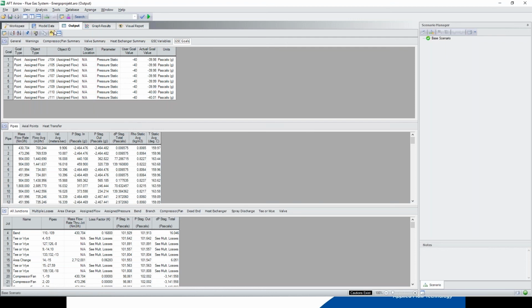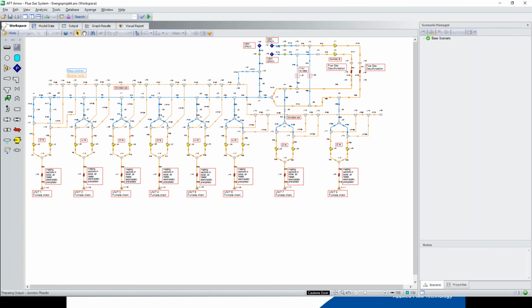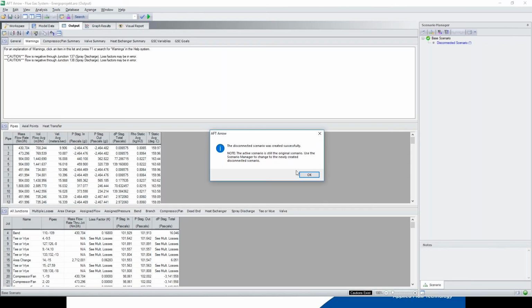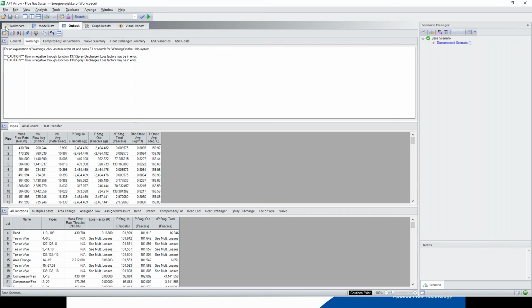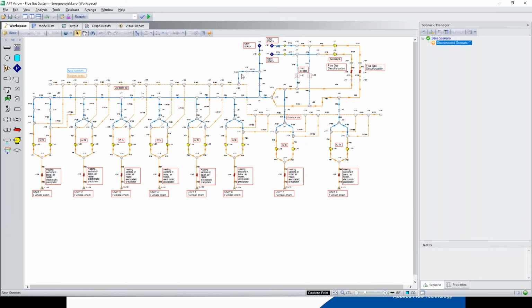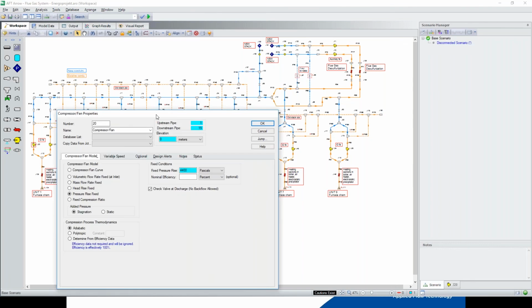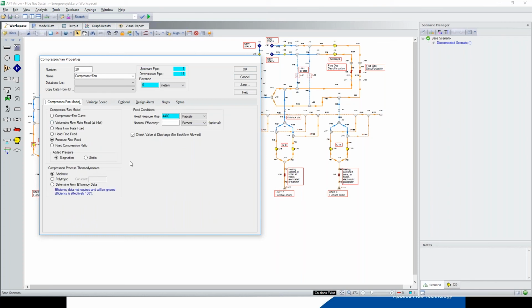So if I hit here, it will create a scenario, and if I go to workspace, wait, let me go to output. So here's this disconnected scenario, and for each one of the fans in this disconnected scenario, we have a control set to achieve the fixed pressure rise that is required to achieve the minus 40 Pascals in each one of the flow supplies of the system.